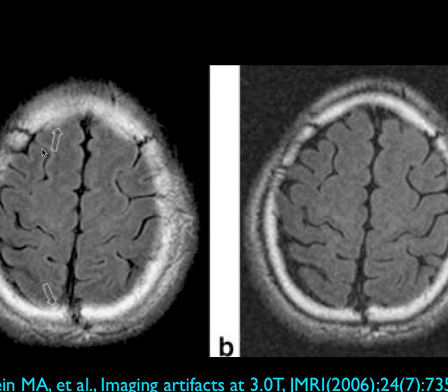And what happened here is the fat slice, the lower frequency direction, is toward the top of the head. So this band here is actually the fat within the marrow space, which is basically a slice above the water signal, which is in the brain here. And it superimposes the fat within the marrow space onto the brain because of the chemical shift artifact in the Z direction.